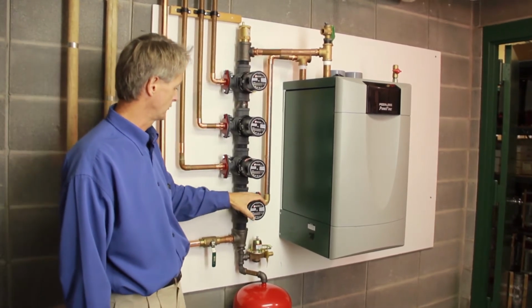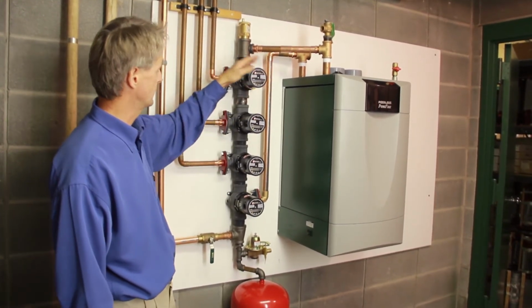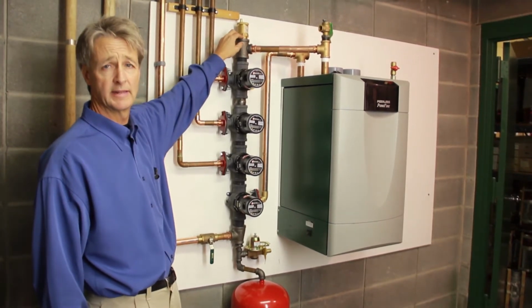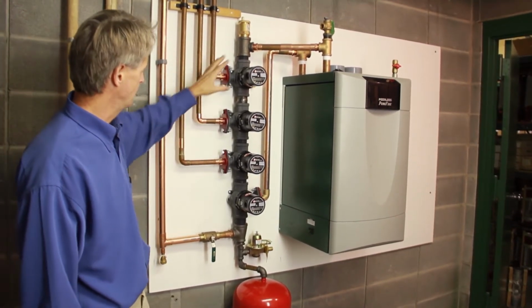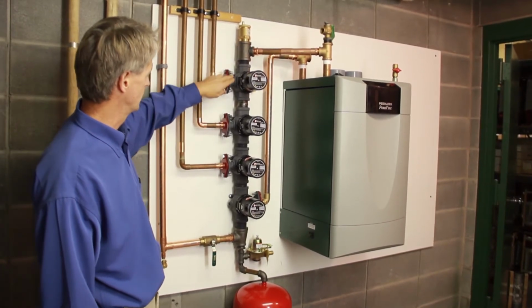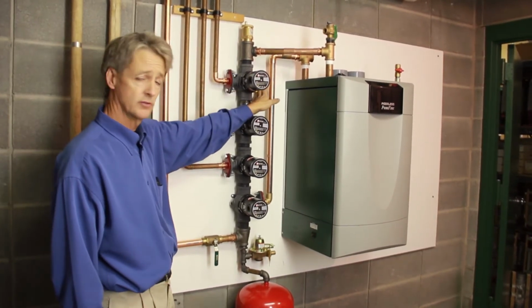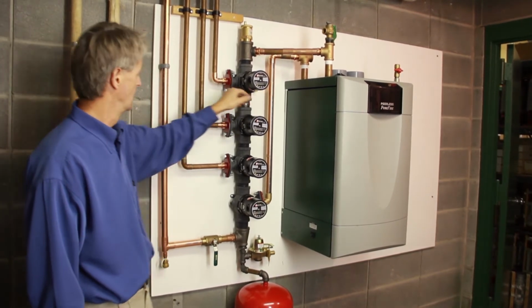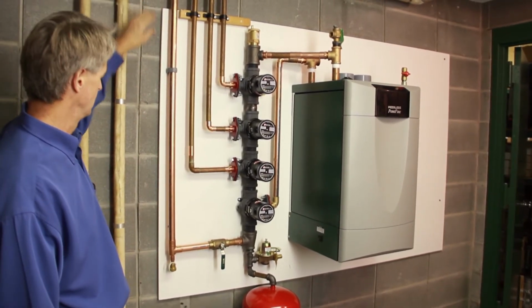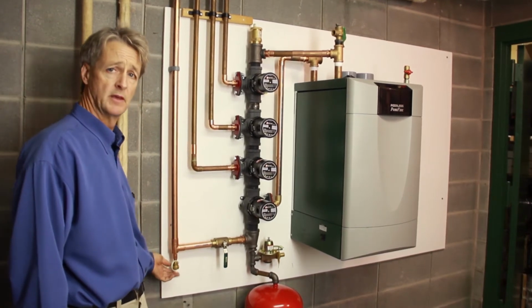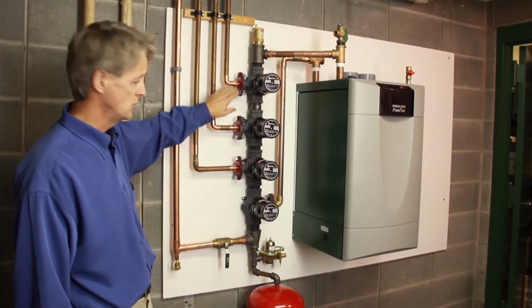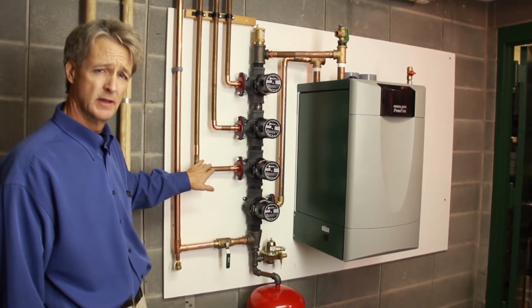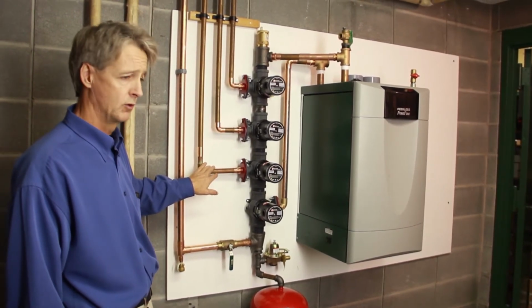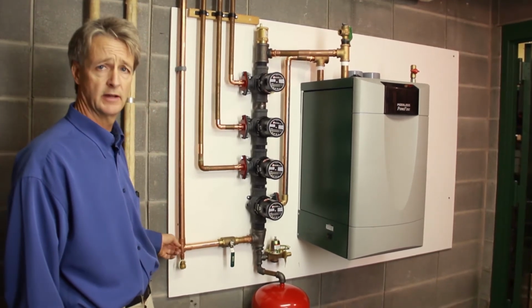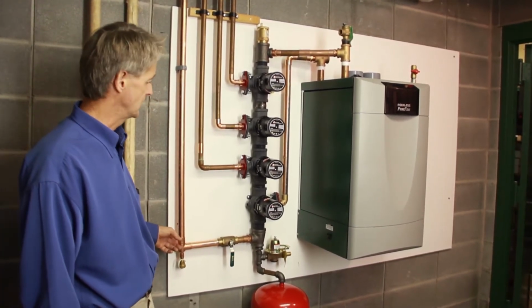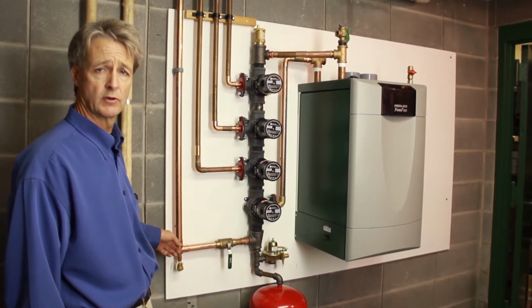Once we turn the boiler circulator on, it'll drive the air out through velocity to the heat exchanger, and we become completely flooded in the heat exchanger. Once this portion of the system is flooded, we can go zone by zone, opening up the suction isolation ball valve, letting the fluid flow through the circuit and purge out the common return line. So when the first zone is purged, we move on to the second and then to the third. We're able to power purge this system very quickly with only one drain connection on the system. Once the system is flooded, it's very resistant to any future air binding.